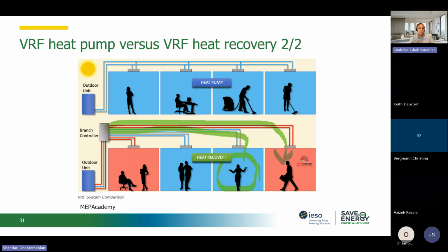Because this is waste heat that needs to be removed from, let's say, these two areas, and now that heat can be dumped in the other. And if extra heat is necessary, then the outdoor unit starts to work and brings the extra heating that is necessary. So heat pumps these days can also be designed to have heat recovery. It's just a design; you don't need anything extra. If you have one outdoor unit and a branch controller, with the proper settings it can take the heat to the branch controller from those areas that need cooling and dump that heat to the areas that require heating at the same time.